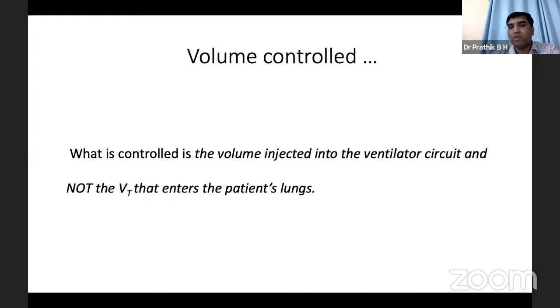But in volume controlled ventilation, what is controlled is the amount of volume which is injected into the ventilator circuit. It is not the tidal volume which enters the patient's lung. Here you can see the patient's lung is only a part of the circuit system. What is controlled in volume controlled ventilation is the amount of volume which is delivered from the ventilator, and it is not the amount of volume which enters the patient's lung. The volume delivered from the ventilator depends on so many factors, like compliance of the tubing, the compressible volume of the circuit, the humidifier, and the leak around the endotracheal tube. So whatever tidal volume has been delivered at the ventilator end may not be exactly reaching the patient end. So this was one of the fallacies or problems with volume controlled ventilation.